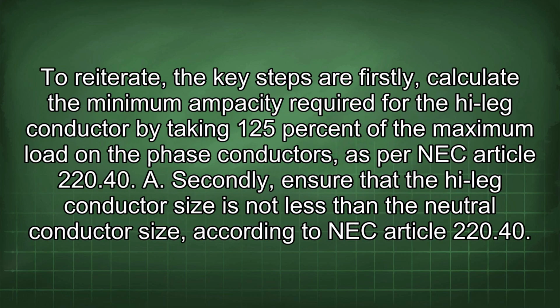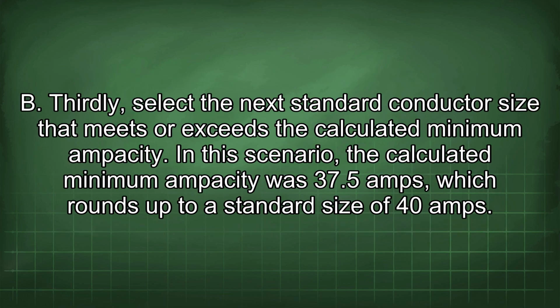To reiterate, the key steps are: firstly, calculate the minimum ampacity required for the high leg conductor by taking 125% of the maximum load on the phase conductors, as per NEC Article 220.40. Secondly, ensure that the high leg conductor size is not less than the neutral conductor size according to NEC Article 220.40. Thirdly, select the next standard conductor size that meets or exceeds the calculated minimum ampacity. In this scenario, the calculated minimum ampacity was 37.5 amps, which rounds up to a standard size of 40 amps.